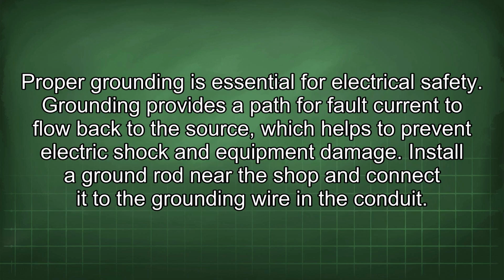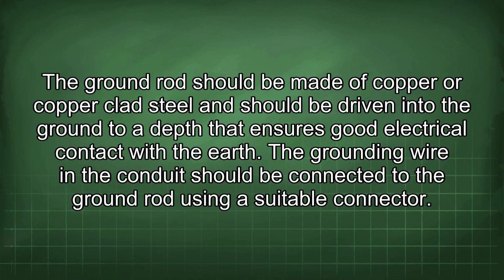Use appropriate fittings to connect the conduit sections and to attach the conduit to electrical boxes or equipment. Proper grounding is essential for electrical safety. Grounding provides a path for fault current to flow back to the source, which helps to prevent electric shock and equipment damage. Install a ground rod near the shop and connect it to the grounding wire in the conduit. The ground rod should be made of copper or copper-clad steel and should be driven into the ground to a depth that ensures good electrical contact with the earth.